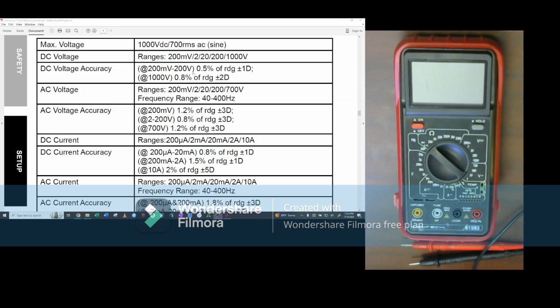So these are good little meters. Our AC voltage, we have different ranges. And the one thing we need to know is with AC voltage, what is our frequency range? If we exceed this frequency range for AC voltage, the DMM will actually change internally and give us faulty values. So in this case, this DMM that we have has a minimum of 40 and a maximum of 400 hertz. So those are the absolute limits of what we can put through this thing. No more, no less. That's what we're after.